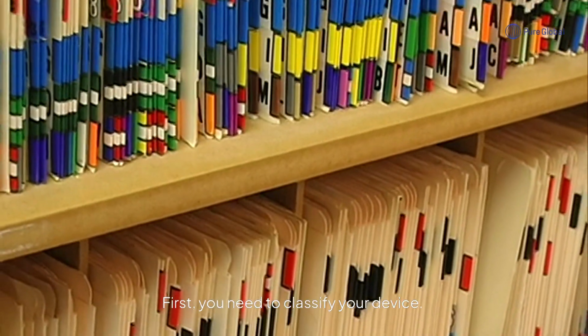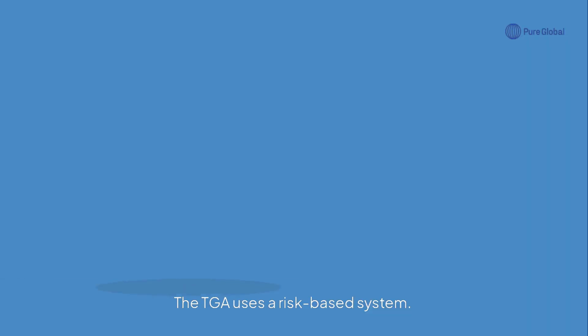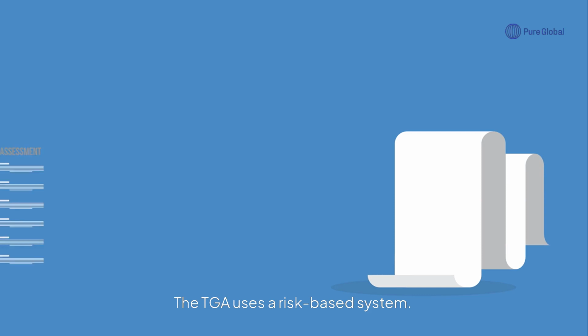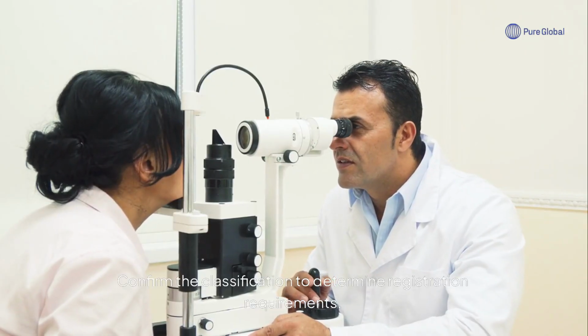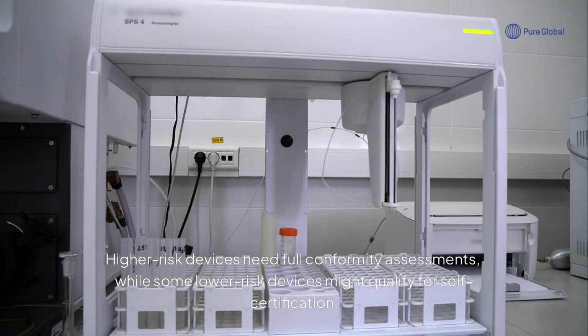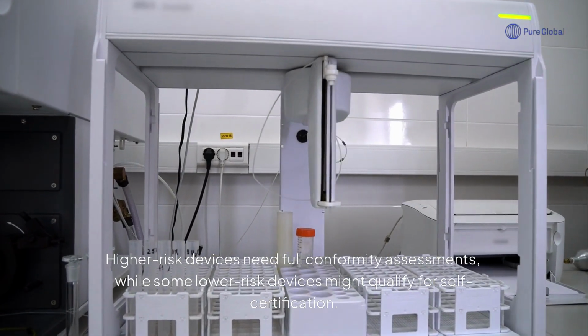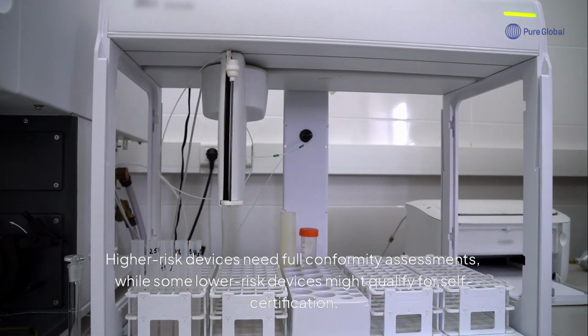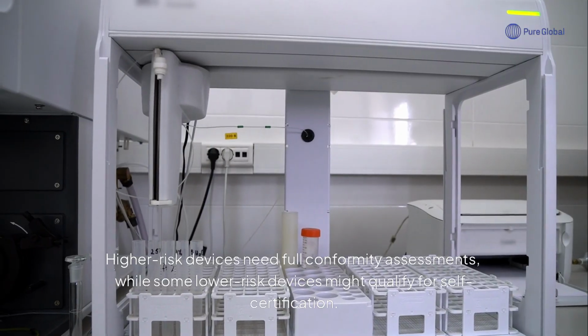First, you need to classify your device. The TGA uses a risk-based system. Confirm the classification to determine registration requirements. Higher-risk devices need full conformity assessments, while some lower-risk devices might qualify for self-certification.